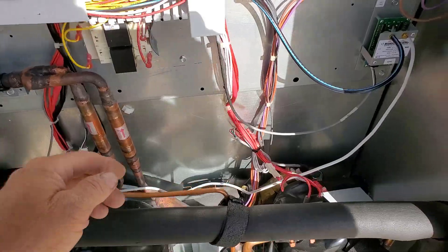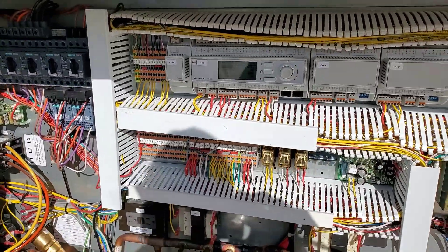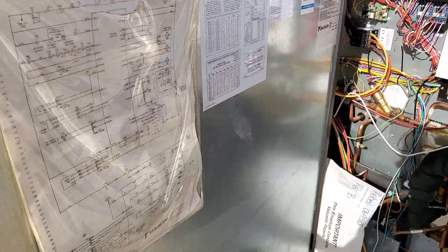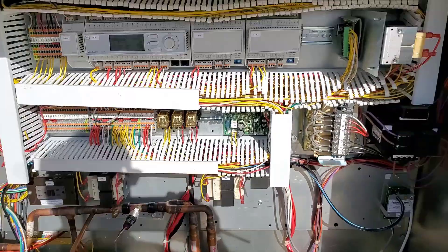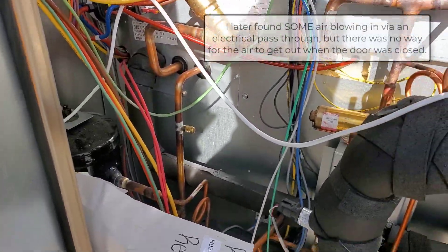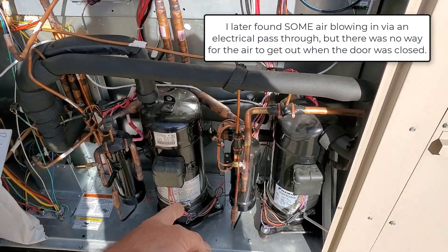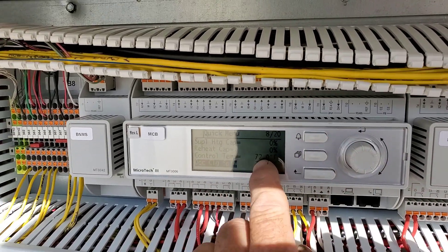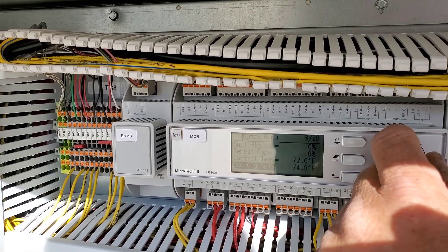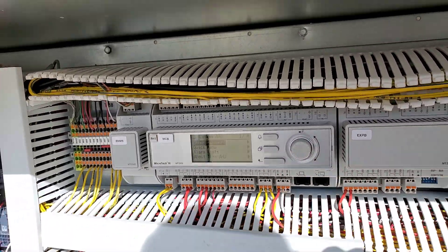This panel is falling off. These are insulated panels - I think AAON has foam in between their panels and blows air through this chamber. Maybe this one doesn't have that and just has extreme temps in here. Those are rotaries, so this whole shell is as hot as it can be when those things are running. You'd think there'd be air passing through this chamber to control temp. It's reading 72 degrees, and the cooling setpoint is at 74, so the unit's not going to run.